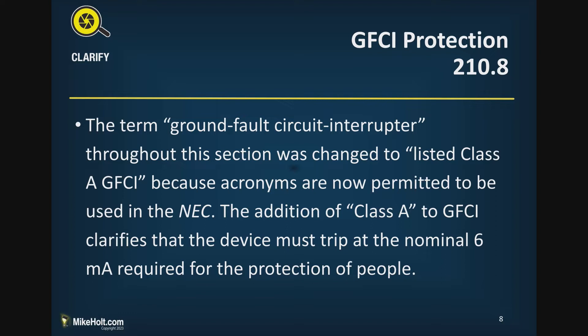I have to add that nominal six milliamp requirement for the protection of people. Now, I thought GFCIs tripped at five milliamps. Well, here's what I've always said — we have to change our text and our graphics. Thank you Eric for yesterday's conversation. GFCIs have to trip at six milliamps or above. But if you look at the informational note in Article 100, it says GFCI — I think it says in there it can't trip below four milliamps but it has to trip over six milliamps.